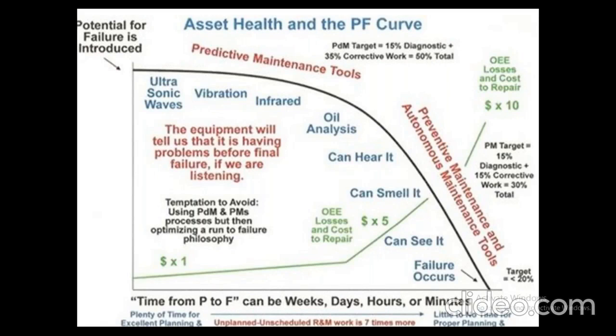We are not limiting the energy audit to a given textile mill or to any one industry. This is typically meant for an industry where maintenance goes from predictive maintenance to preventive maintenance to breakdown maintenance. You can see the potential for failure can be measured by ultrasonic waves. We are using these ultrasonic waves. The sonic imager is gradually, it is in the nascent stage. It has started gradually entering the industry now. And for any of the motors, especially alignment, you see, textile mill is an alignment oriented industry. Here the alignment is more critical, more important.